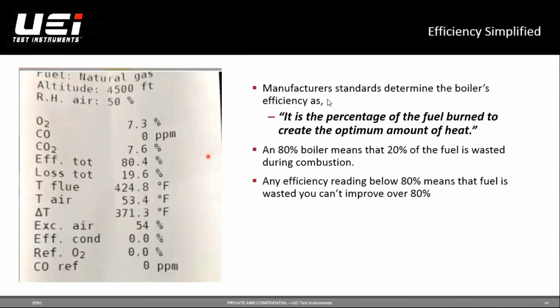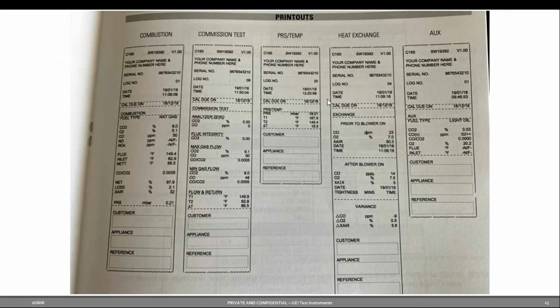Every manufacturer determines their boiler efficiency. We talked about 80% boilers meaning that 20% of the fuel is wasted. The other important thing to remember is don't go chasing the efficiency. I've seen too many contractors who think, if I crank up the gas pressure here, I'm getting 83%, which in theory sounds fantastic, but now you've taken that unit outside of the manufacturer specs for gas pressure, and that can lead to a whole lot of other issues.